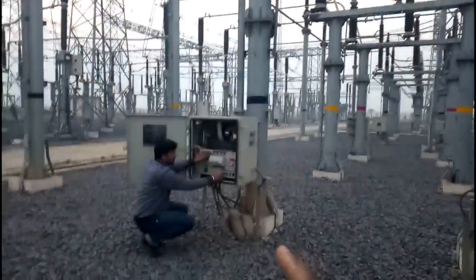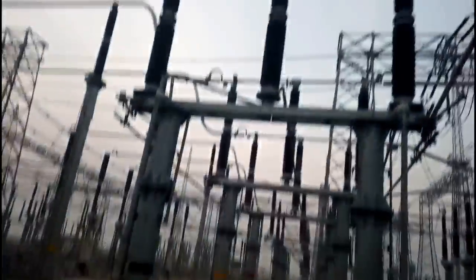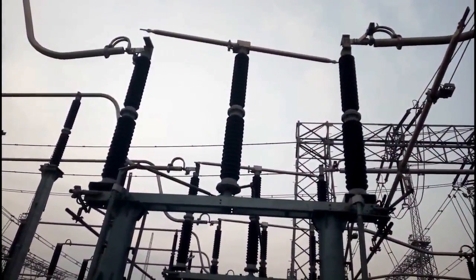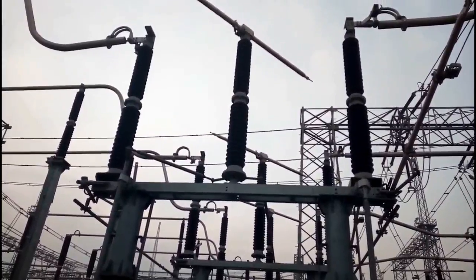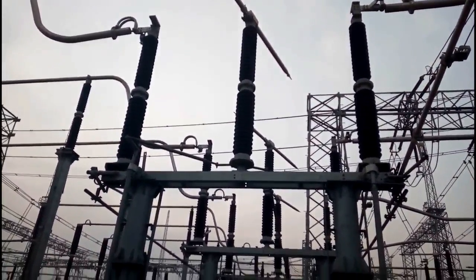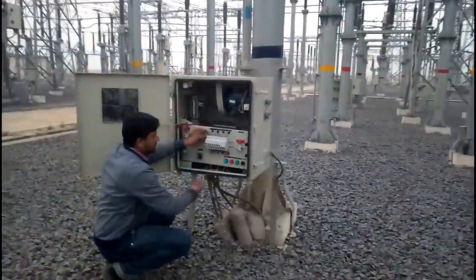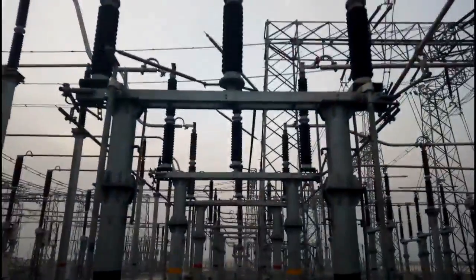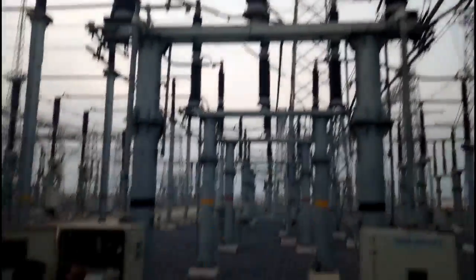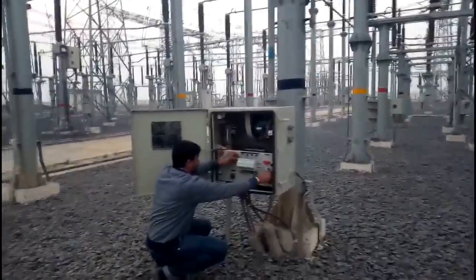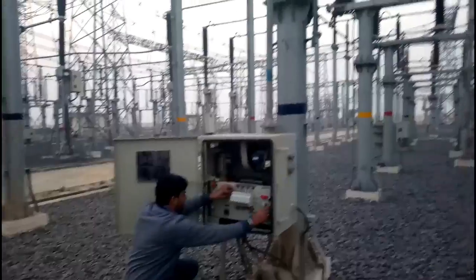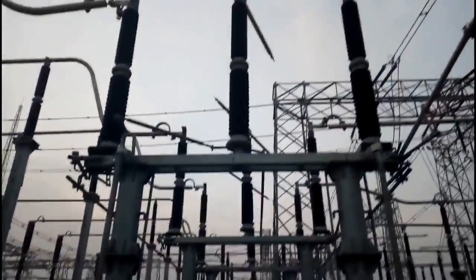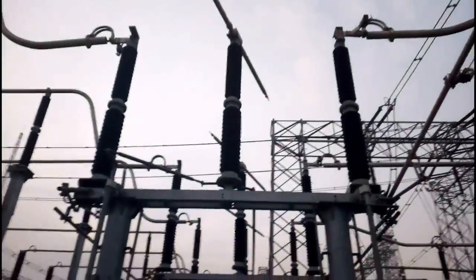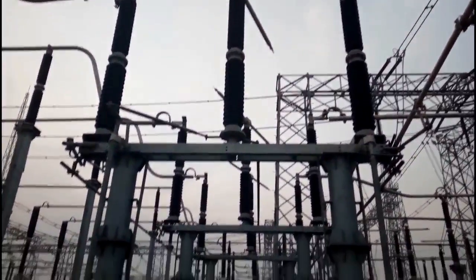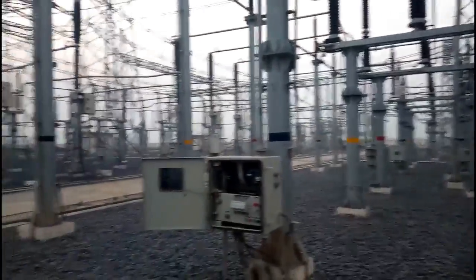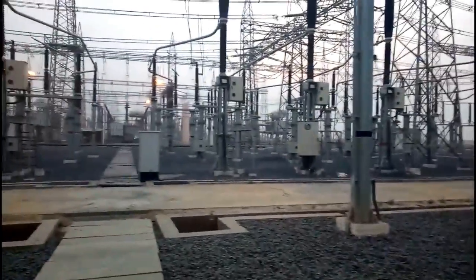Now can you please give the open command? He has pressed the open command, and see here that this isolator disconnector switch is open. See, R phase, Y phase, B phase, all three poles are open now. Off. So like that the operation happens for the disconnector switch. From local we can operate using this mechanism box, and when we want to operate this disconnecting switch from the SCADA control room, we can give the command from there, and we can give the command from the relay also, and in such a way this disconnector switch will be operated.